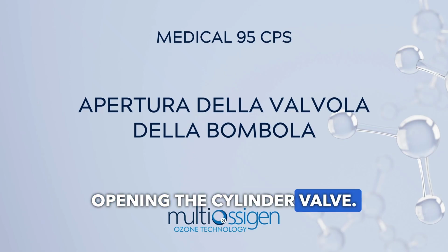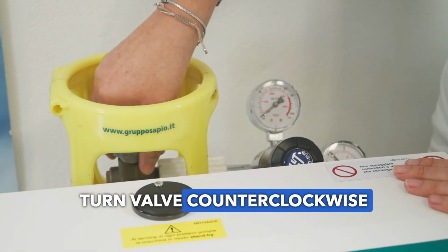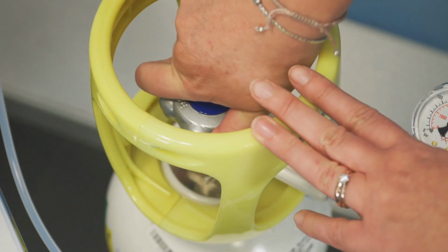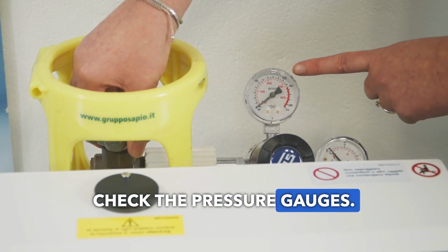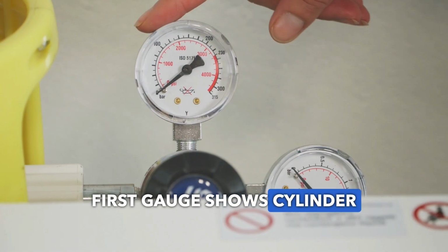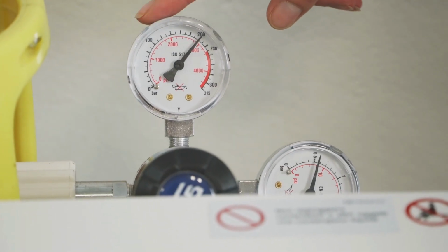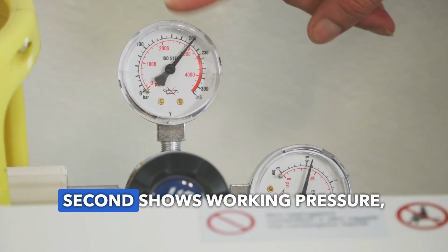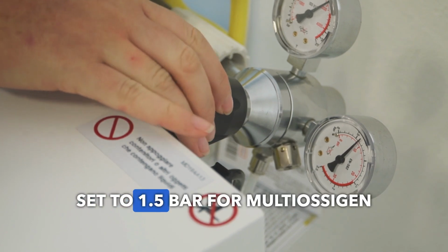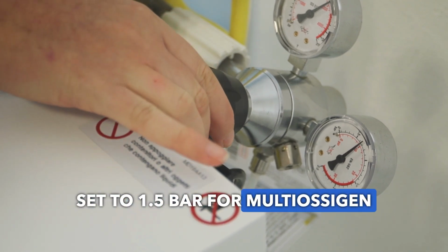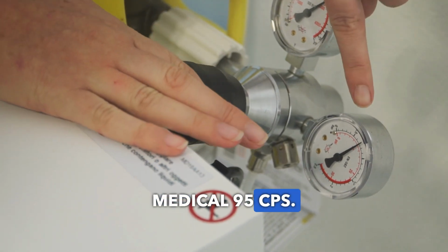Opening the cylinder valve. Turn valve counterclockwise to open. Check the pressure gauges. First gauge shows cylinder pressure. Second shows working pressure, set to 1.5 bars for Multiossigen Medical 95 CPS.